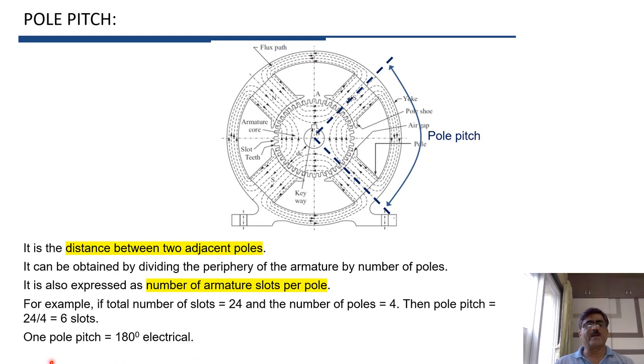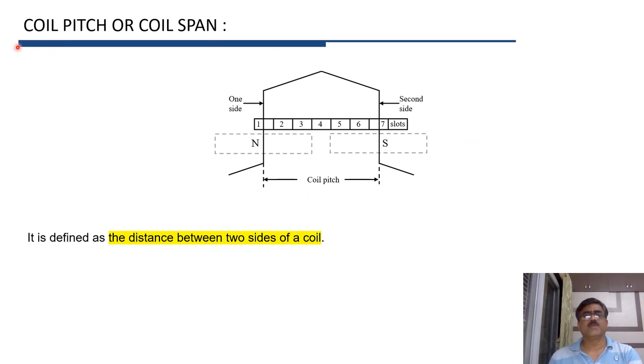One pole pitch is always equal to 180 degrees electrical. The next important term is coil pitch or coil span — the distance between two sides of a coil. Coil side 1 is placed in slot 1 and coil side 2 is placed in slot 7, and the distance between these two coil sides is called the coil pitch.